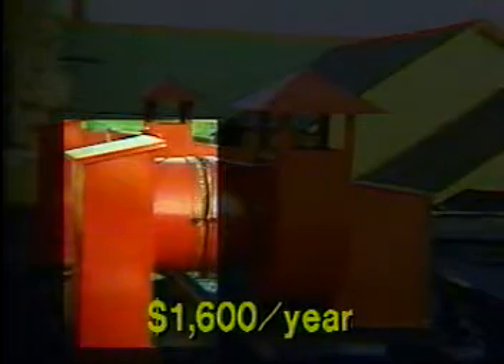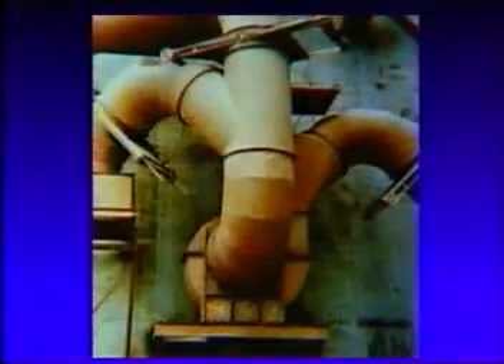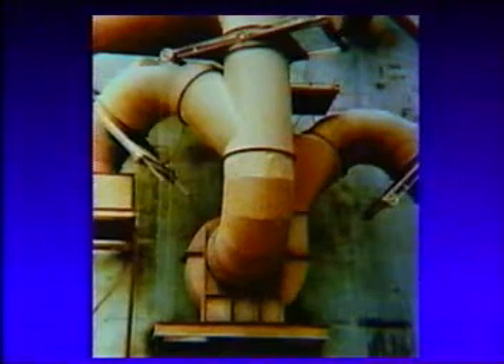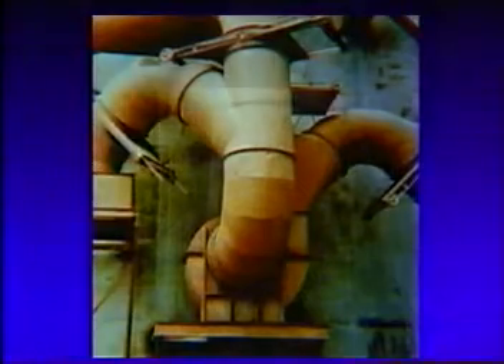by $1,600 per year. Example: a 36-inch fan capable of moving 18,000 CFM was installed with an elbow at the inlet. Moving air through this inefficient system increased energy use and energy costs by $6,100 per year.